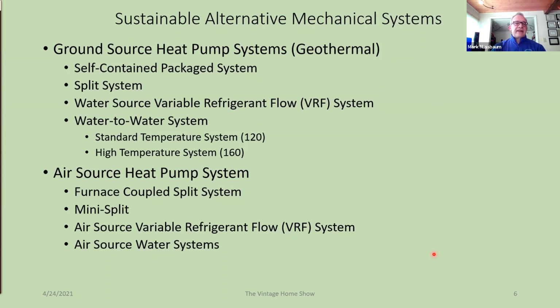You can get a split system, one box outside or one box inside connected to the ground loop, which connects to an air handler or something. I'll go into these in a little bit more detail. You've got a water source variable refrigerant flow, or VRF, system. You've got a water to water system, standard temperature 120 and high temperature of 160. And then with the air source, it's all basically the same equipment, only with an outside box interacting with the air environment instead of the ground environment.